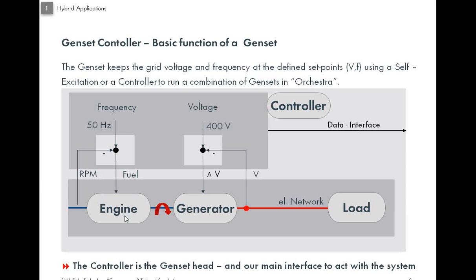So if you see at the bottom, your DG set will have an engine and it will have a generator. And the power coming out of the generator will be flowing to the load. Now, the engine and the generator are both exchanging information with what we call the controller. So your frequency and your voltage data is being captured by the controller. So we can say that the controller is the genset head, and that is the interface with which our PV system is going to interact.